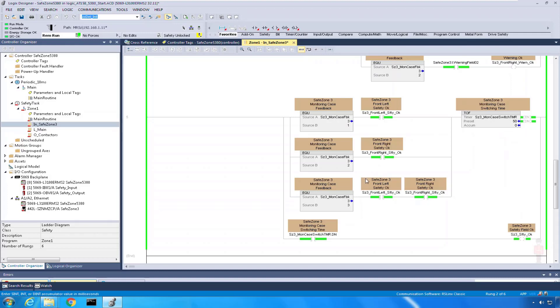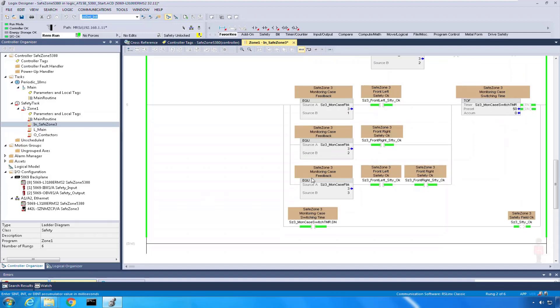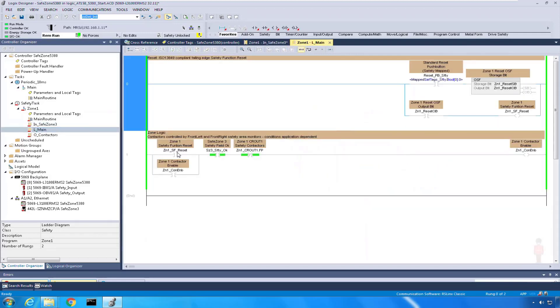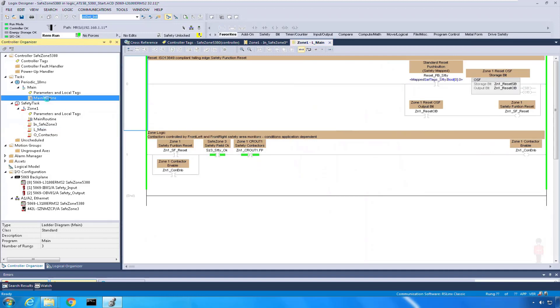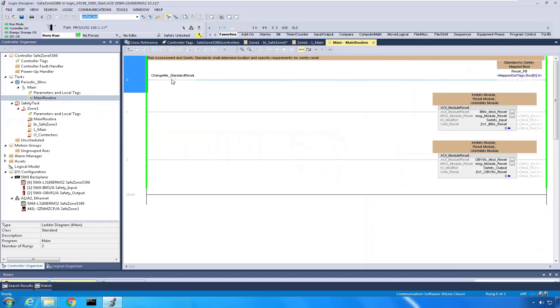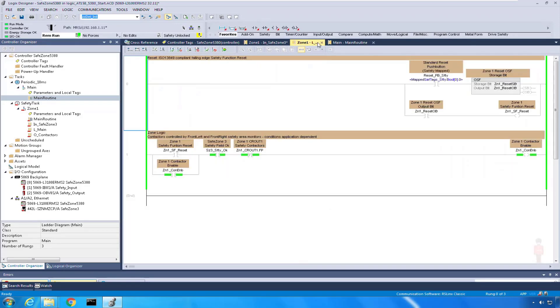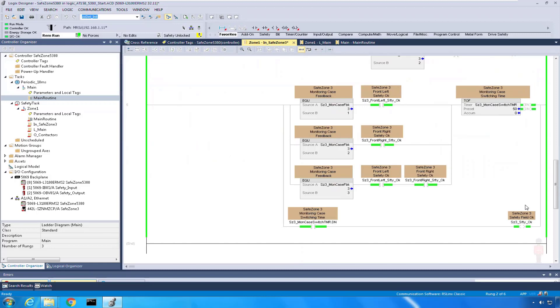This tag then I basically bring to my main and say, hey, if the Safe Zone is okay and my contactors are fine, then turn on. I'm going to give my Safe Zone a reset, a falling edge reset, and you'll see that my main is now turned on. You may have heard my contactors come on, but as long as the Safe Zone 3 is repeating or observing that safety is okay, they will stay on. But it'll go off as you may have heard in the background. You saw the blip, and that's really all I'm doing for the logic.